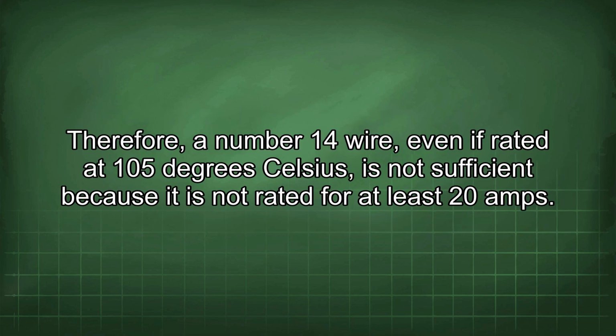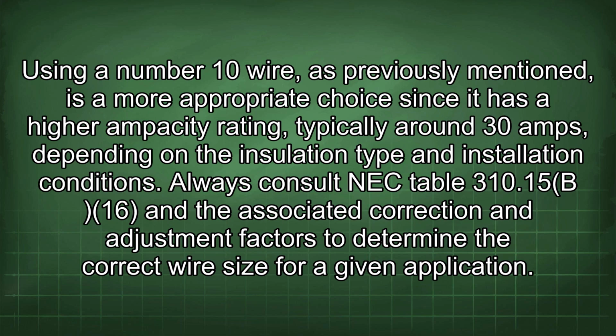Therefore, our number 14 wire, even if rated at 105 degrees Celsius, is not sufficient because it is not rated for at least 20 amps. Using a number 10 wire, as previously mentioned, is a more appropriate choice since it has a higher ampacity rating, typically around 30 amps, depending on the insulation type and installation conditions. Always consult NEC Table 310.15(B)(16) and the associated correction and adjustment factors to determine the correct wire size for a given application.